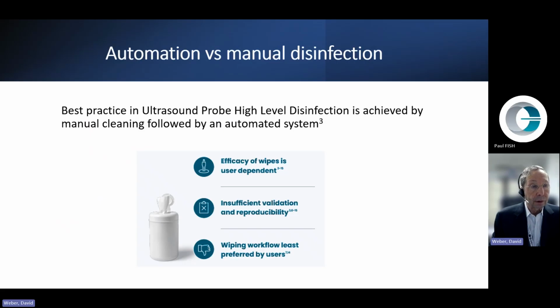Best practice in ultrasound probe high-level disinfection is achieved by manual cleaning followed by an automated system. The efficacy of wipes is user-dependent. It's easy to miss spots on a probe just using wipes. In addition, if the wipe dries out, it doesn't have adequate chemical disinfection. For the use of wipes there is insufficient validation and reproducibility, which has been shown. And the wiping workflow is the least preferred by actual users of ultrasound probes.